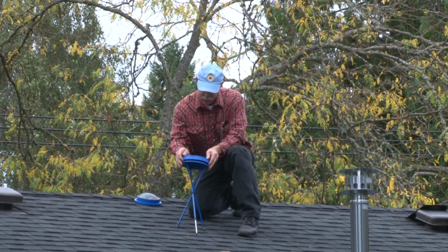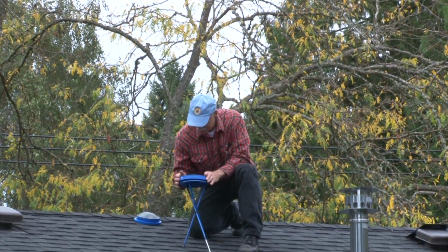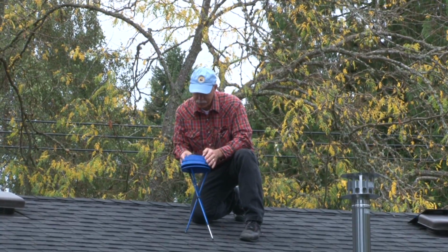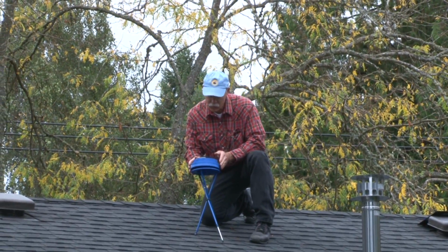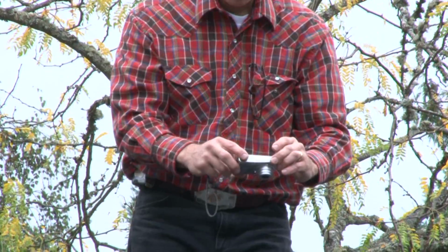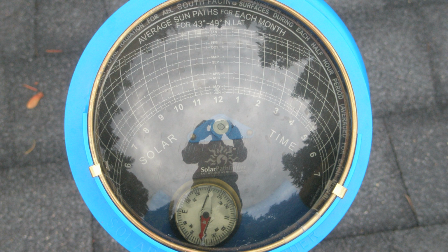The Solar Pathfinder is a much simpler solar resource tool that uses a compass, a leveling bubble, and interchangeable paper sunpath charts under a transparent but reflective domed lens. The sunpath charts show the daily path of the sun for each month of the year. The dome reflects the image of all surrounding solar obstructions, allowing the technician to take a photo that captures both the sun chart and the obstructions in one image.